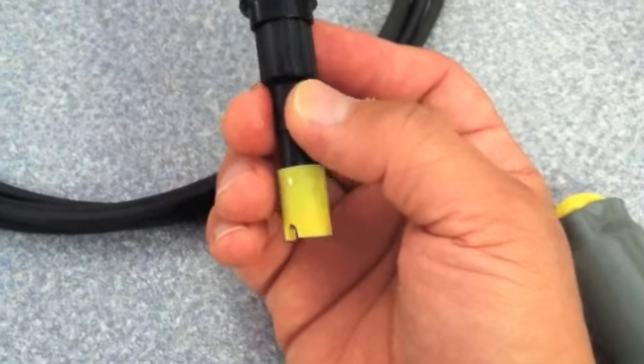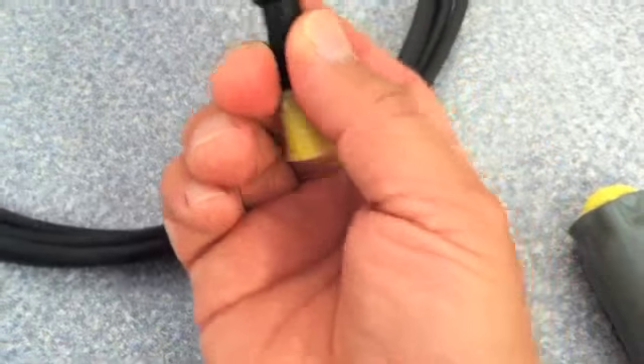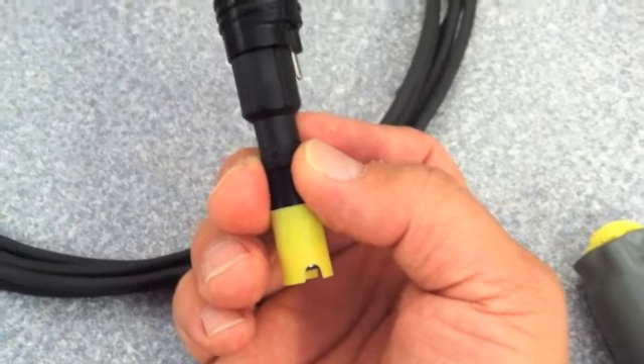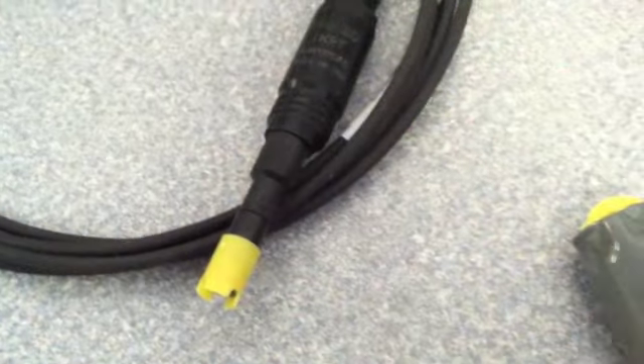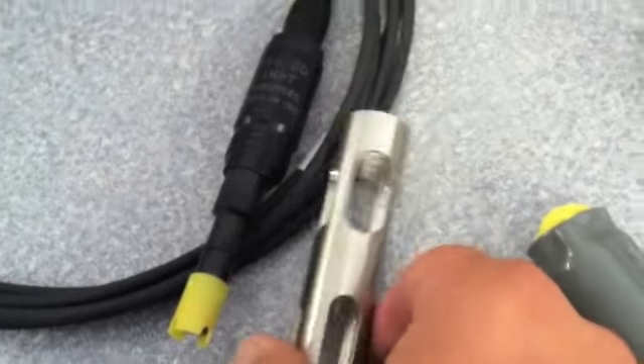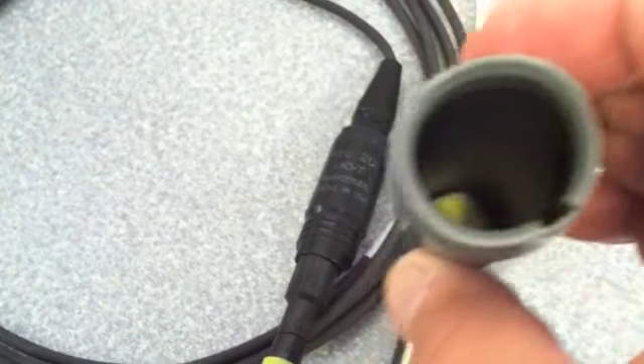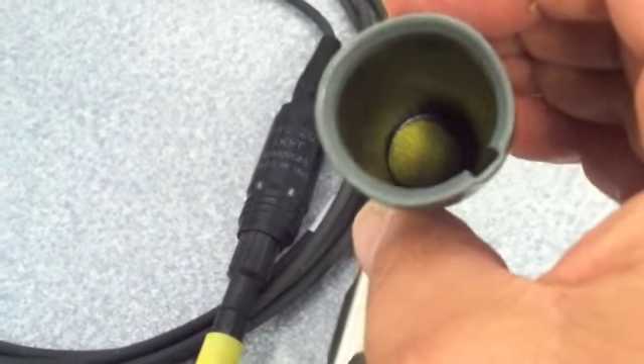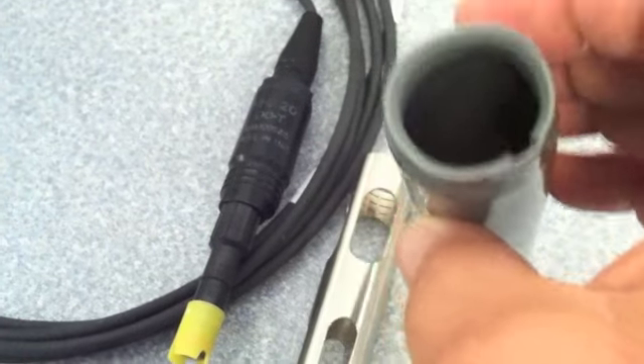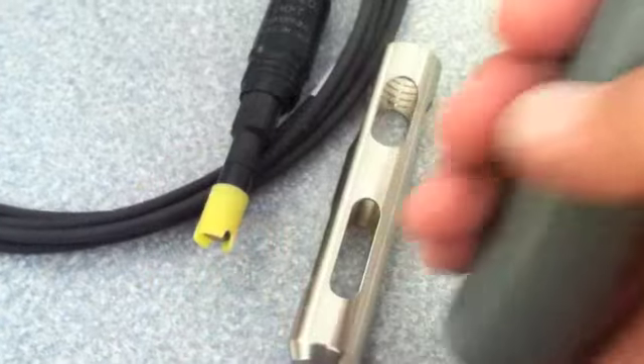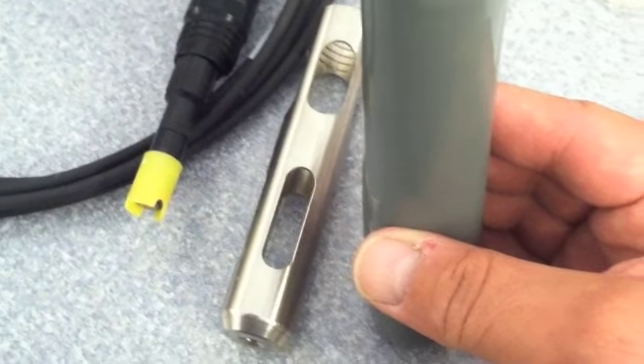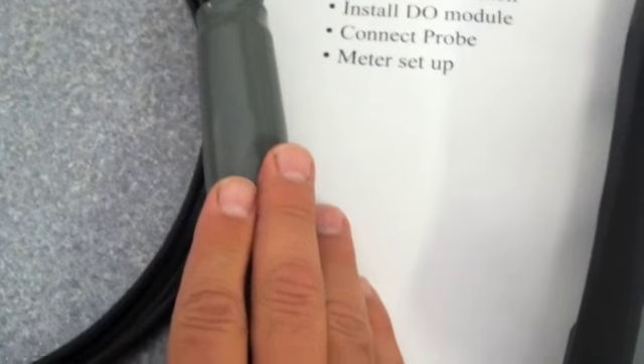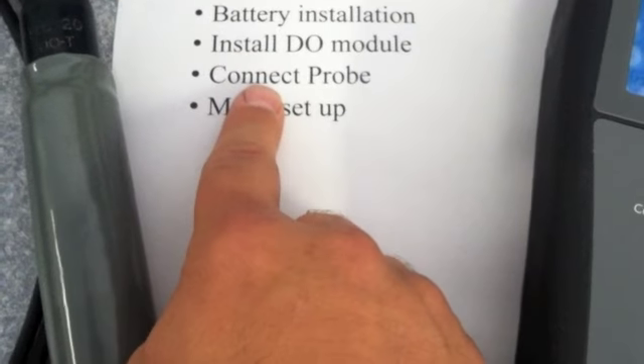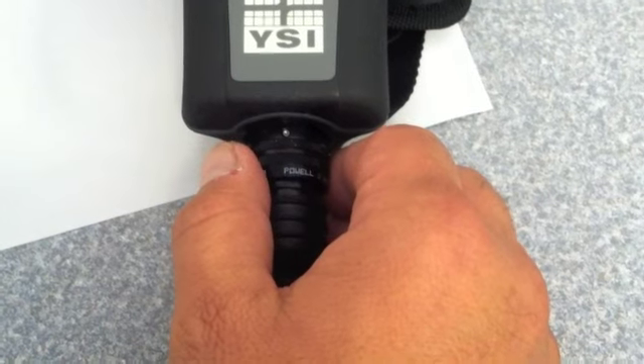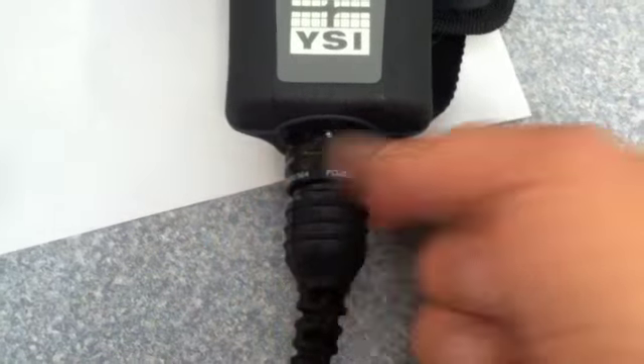I rinsed the DO module with some distilled water, and we screwed on the cap, and the probe is ready to go. We'll put on the probe guard, and in the calibration sleeve we're going to put the sponge, and we're going to add just enough water to keep that sponge moist. That's important for not only the storage but also for calibration. So we have the calibration sleeve on, and then as far as connecting the probe, there's a military connector here. We just lined it up and twisted it.